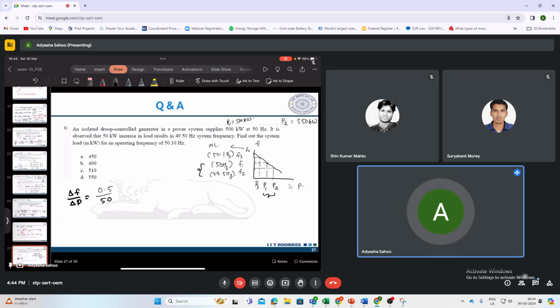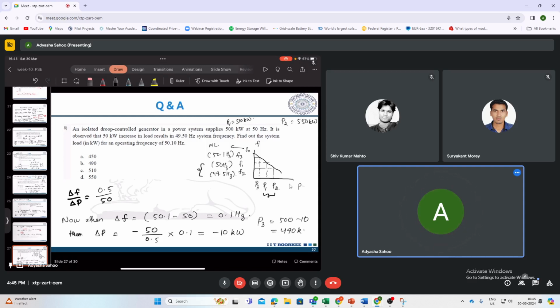Now when delta F is 50.1 minus 50, that is 0.1 hertz, then delta P will be this slope into the change in frequency. So what will that be? That is minus 10 kilowatt. So the drop in load will be 10 kilowatt. So P3 will be 500 minus 10, means 490 kilowatt. Right.